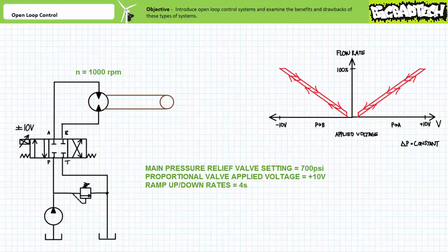When voltage to the proportional valve is linearly ramped from 0 to positive 10 volts over the course of four seconds, the spool progressively shifts to the full straight-through position. Flow rate to the hydraulic motor goes from 0 to maximum. The unloaded conveyor belt accelerates and stabilizes at 1600 RPM — a little too fast for our particular application. While the conveyor belt is running, the technician then dials down the voltage to the proportional valve until speed stabilizes at the desired 1000 RPM. Let's say this new voltage value is equal to positive 5.4 volts.